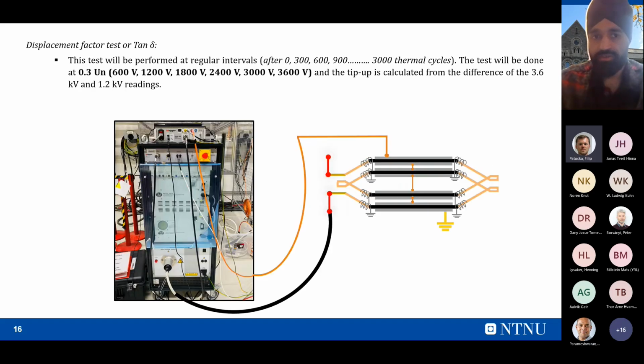The setup for the measurement of tan delta is shown here. For the measurement, we have to de-energize each coil and disconnect it from the other coils, because we cannot measure the tan delta with all three coils connected together. So I have to dismantle everything and de-energize every coil, and only then can I measure the tan delta for this particular system. At their end points, we have to keep some grounding guard wires, otherwise they will give an error in the measurement because of the ground currents. We only measure the currents flowing through the insulation, not the surface currents. Some surface currents will also flow during the measurement, so we need to keep them grounded and measure only the current flowing inside the insulation, that is the leakage current.